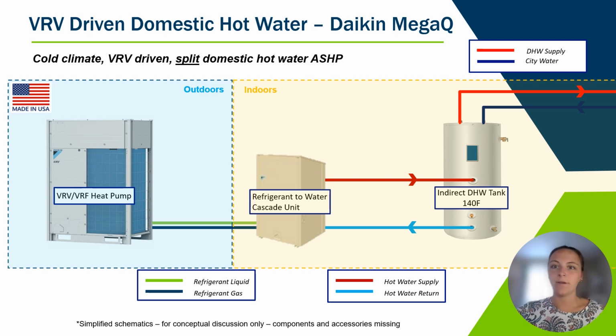And one of the major benefits of having this split system set up with these separate circuits is you can have the VRV heat pump located outdoors with only refrigerant piping needing to be outdoors and no water piping. And that eliminates the need for a glycol or heat trace. And this cascade system can produce water up to 194 F at -4 ambient and allows for efficient air source heat pump operation and hot water production at both high and low lifts, unlike some other solutions like a CO2 domestic hot water heater, for example, which does well with high lift but will rely on electric resistance swing tanks at low load. Overall, this is going to be your highest operational efficiency solution for domestic hot water heating.